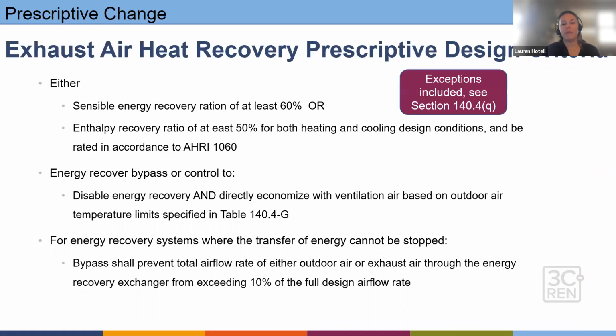And again, one of the main things to pull out of this is you cannot use supply fans to meet the air change requirements anymore. So you either have to use a sensible energy recovery ratio of at least 60%, or use an enthalpy recovery ratio of at least 50% for both heating and cooling.